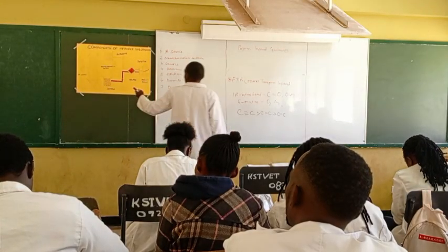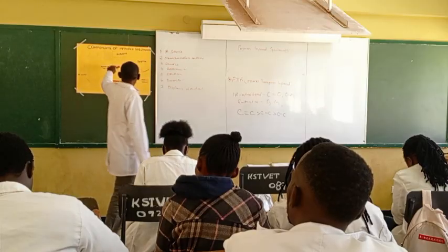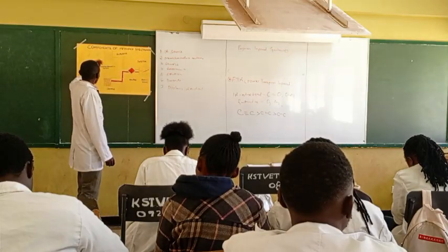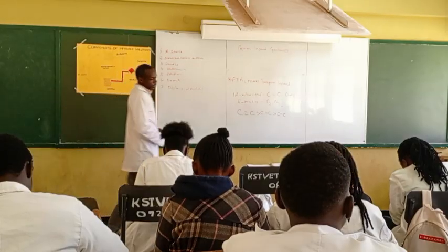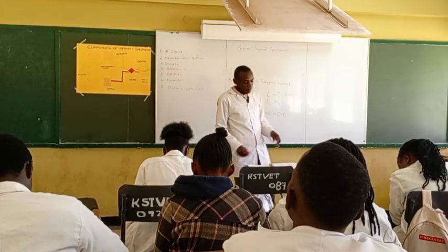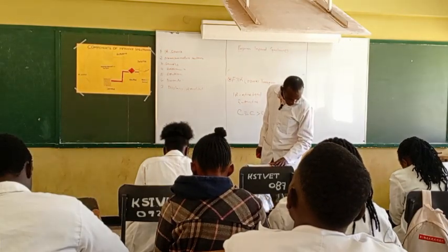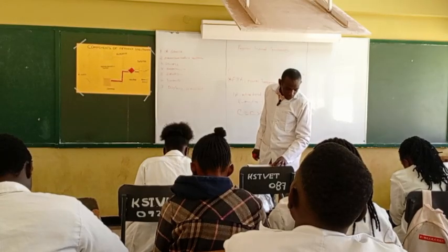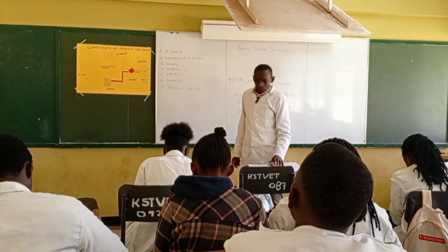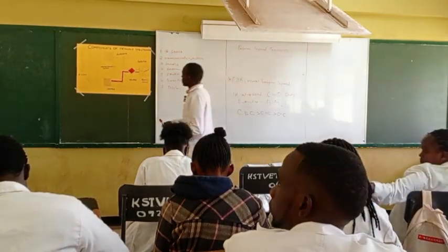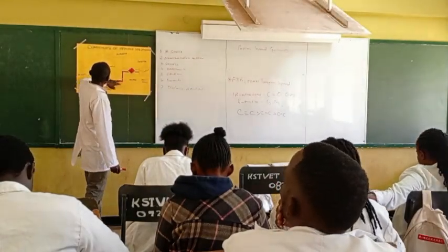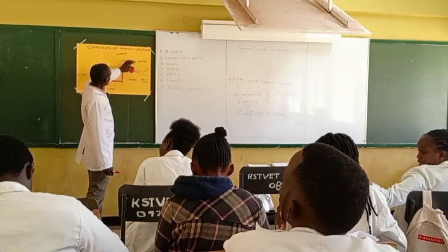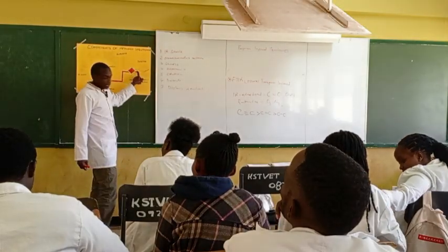And after that, we have the sample and the reference. And then from there, we go to the splitter, where the incoming IR beam is split into two equal parts. You see this one, they're equal actually. They are split into two equal parts, which are going to the detector.